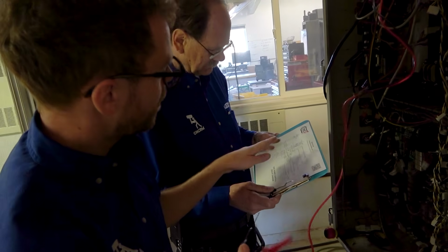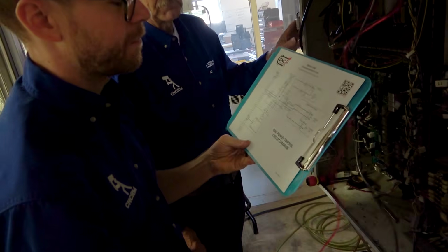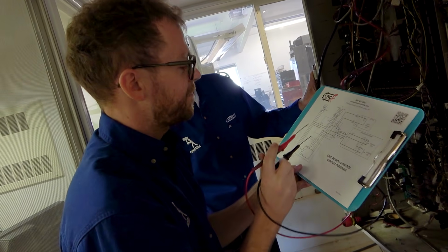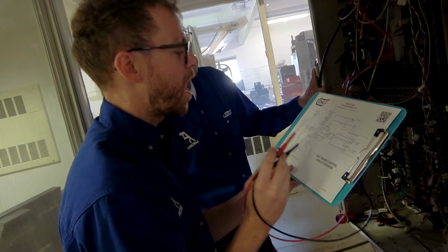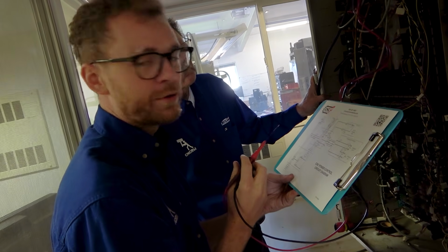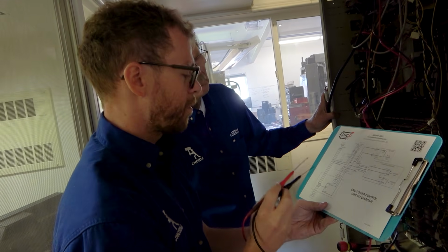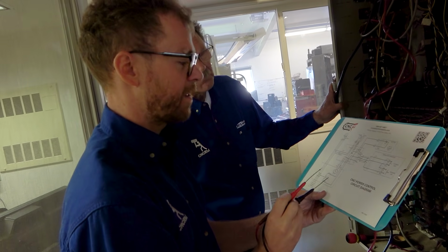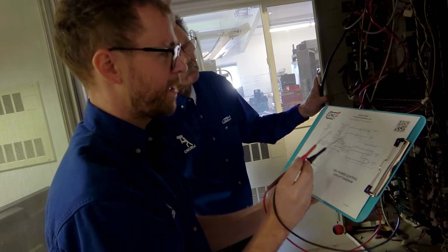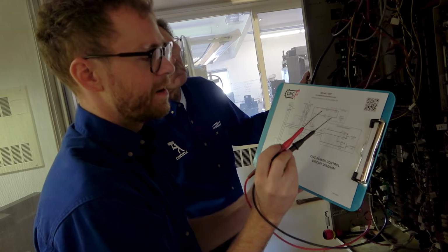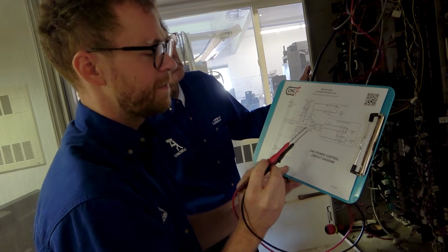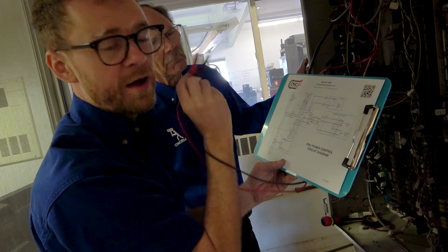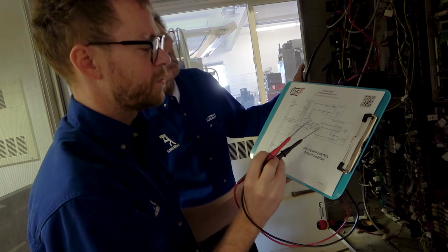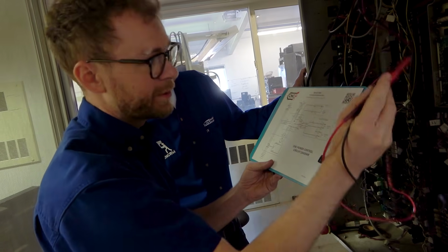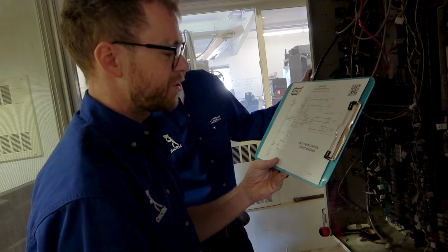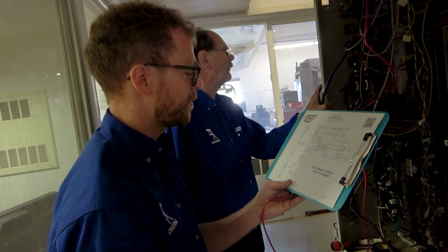Now, on this schematic, I'm going to show you some things that you may not know. Things inside of boxes in the machine tool world are either options on the other side of a terminal strip or inside something. So this box shows everything that's inside of the K1 contactor. This box is showing everything that's in the power distribution board. This box is showing everything that's on the I/O PCB, and this is showing everything that's on the operator pendant up front where the push button is. And in between these two, we have a conduit, the wires leaving here and going all the way to the front. So let's just do a quick walkthrough, and I'll show you everywhere this circuit goes.